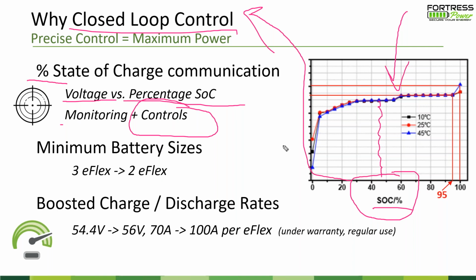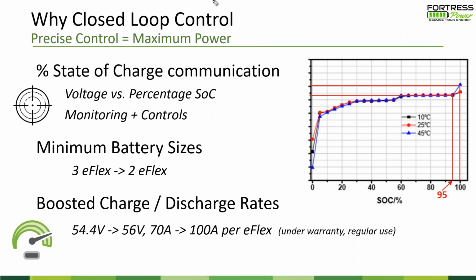The customer doesn't really comprehend the behind-the-scenes controls. What they really want closed loop communication for is monitoring—being able to look at their online monitoring system and see exactly what percent state of charge the battery is at. The only way to do that accurately is with closed loop communication.